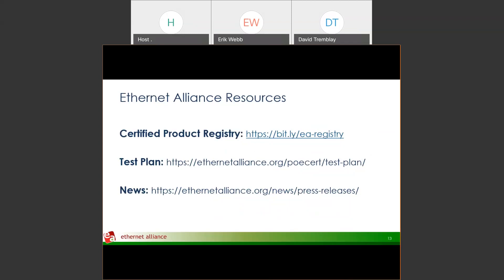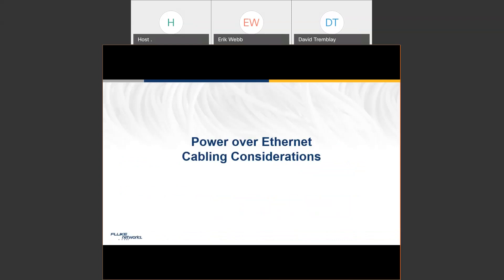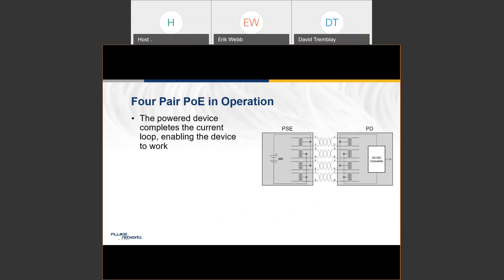Okay, this is Mark. I'm going to talk a little bit about Power over Ethernet cabling. The story we want to tell is that PoE operation is based on the fact that you've got Power Sourcing Equipment, a Powered Device, and that the powered device completes the current loop that allows DC power to flow through the cabling. As David mentioned, there are two-pair and four-pair implementations of PoE. The current needs to be very well balanced across all the different wires used — across all four wires for two-pair, or all eight wires for four-pair.